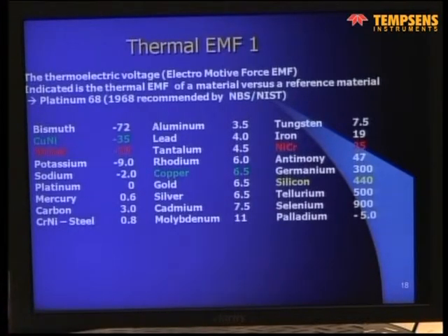Cold junction compensation? Yes, it's cold junction compensation. All the EMF tables in the standard are referenced to 0 degrees centigrade, meaning to the ice point, and not to the water triple point. I don't know why.